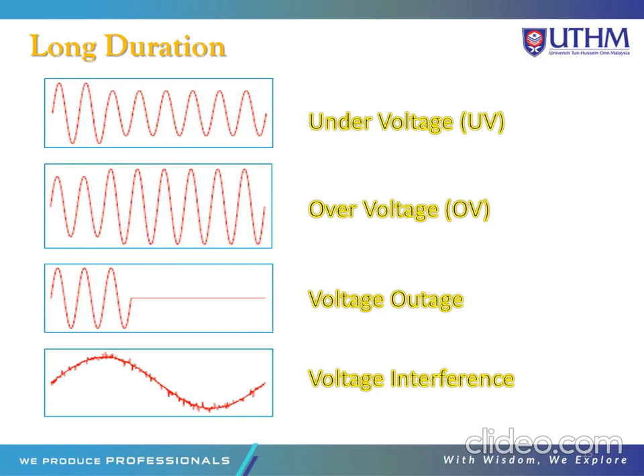For long duration, there are four types of PQ conditions. The first one is undervoltage. We can see here the voltage drop for a certain long period. Then overvoltage. We can see here the voltage is over for a long duration. Then we have voltage outage, where the voltage is zero for a certain long duration. And lastly is voltage interference. We can see here there is interference along the waveform.